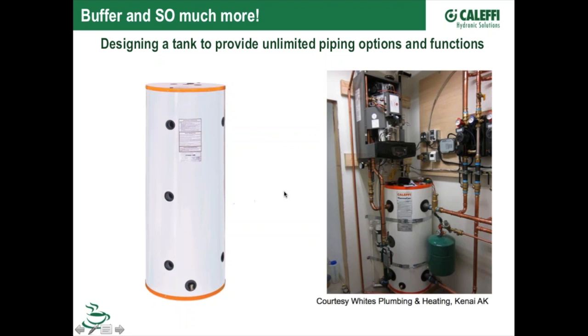So this is a really unique product in that we designed it specifically for that. It's not just a tank like you would buy off the shelf at a supplier. It's a tank that's been engineered to do all these things and do them properly, give you nice piping options here. We do have adapters for that. If you want to put a sensor well in there, we've got bushings that will accommodate that same sensor well I talked about for the hydro separator. It'll take you down to that 6 millimeter, or if you have a different size sensor, you can bush into that.